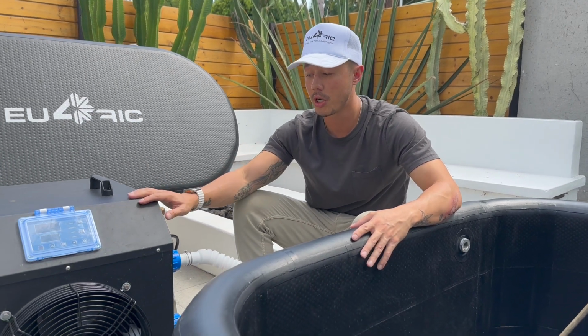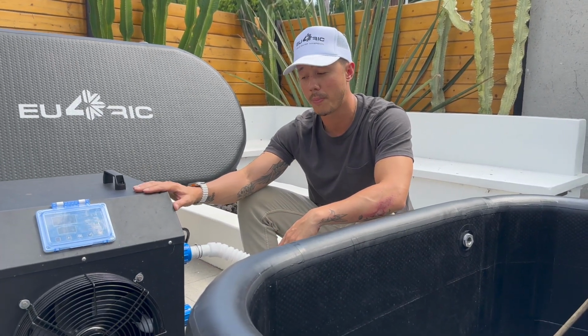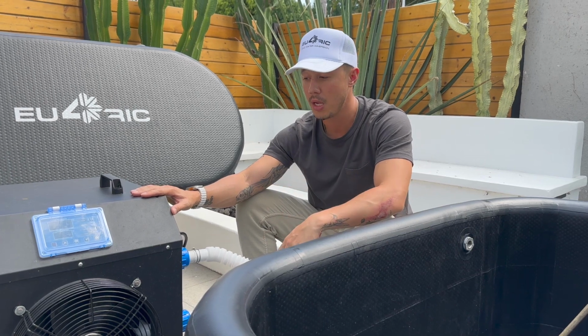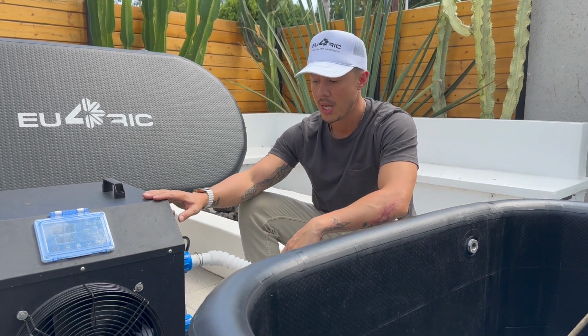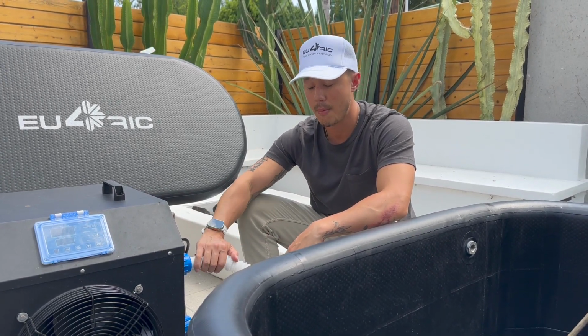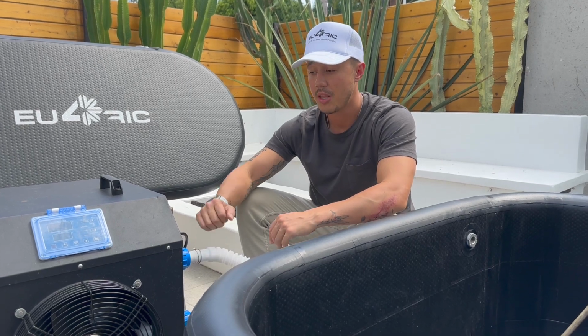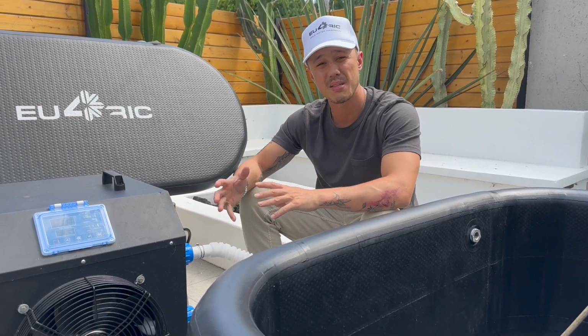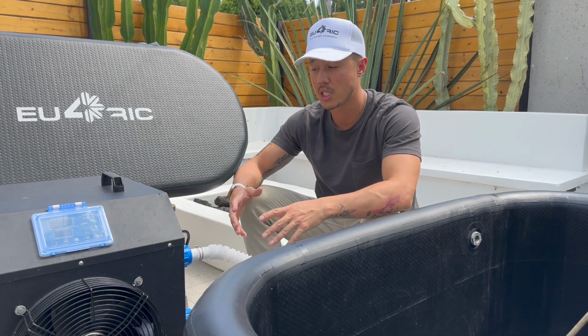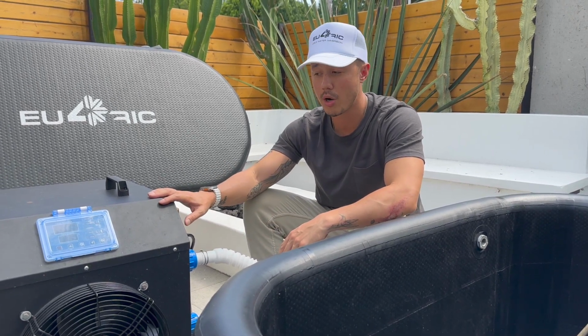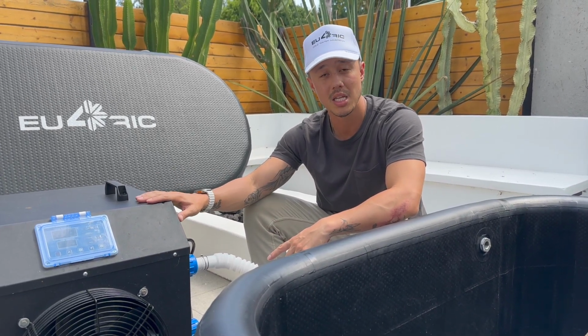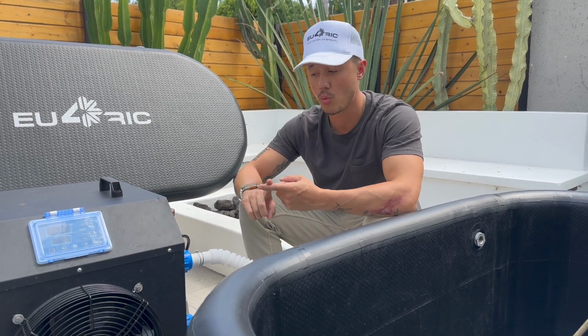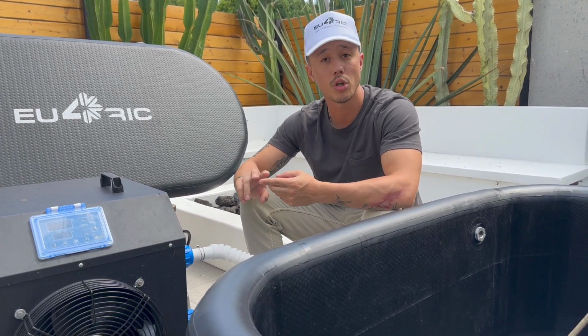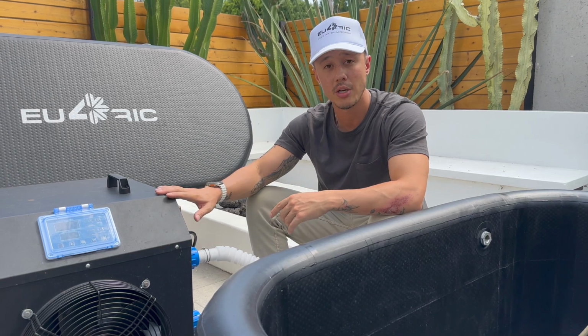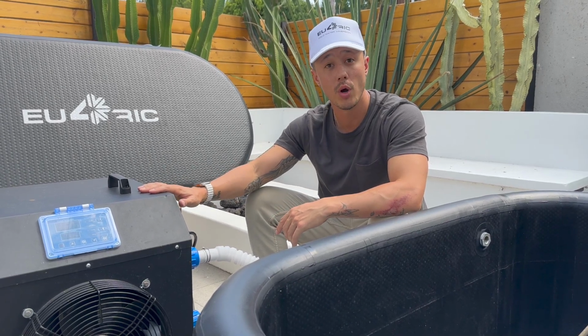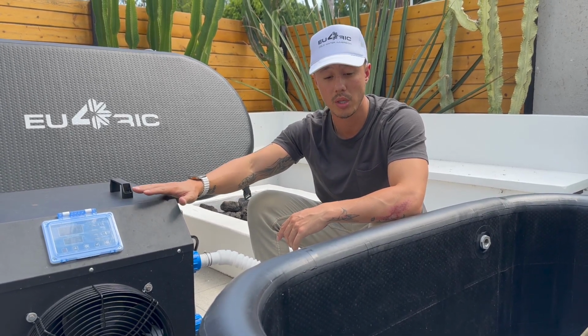A note on the chiller: if you're going to let it sit for a long time without moving it, or store it for a season, make sure that when we unplug these connectors, we tip it on its side and get as much water out as possible. You don't want fresh water sitting in a dark space for a long time—that can cause corrosion and bacteria, which can get you sick, break down your unit, and possibly void the warranty. So make sure we're storing this properly.